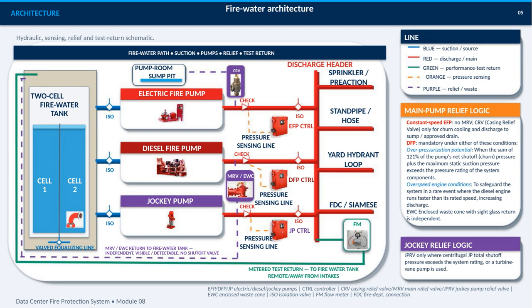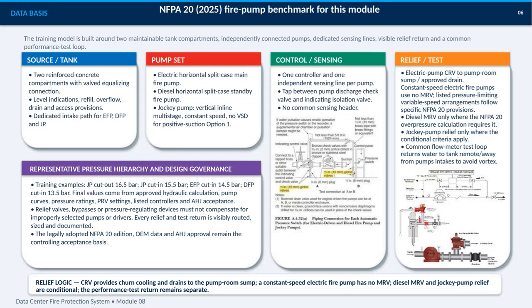The key design principle is that relief, sensing, testing, and return paths remain independent, visible, and appropriately protected from unintended isolation. This slide establishes the data basis for the training model. NFPA 20-2025 is the benchmark used for this module. The system is organized around two maintainable tank compartments, independently connected electric, diesel, and jockey pumps, dedicated sensing lines, visible relief routing, and one common performance test loop.